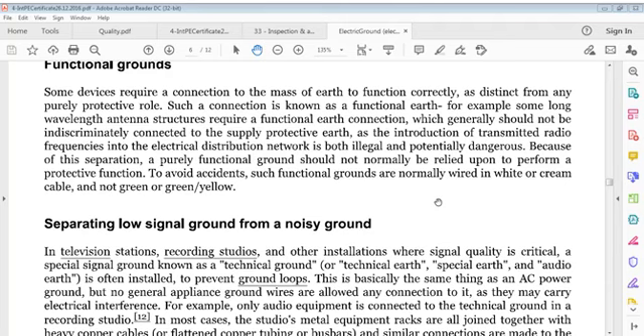What is the reason for that? Some long wavelength antenna structures require a functional earth connection, which generally should not be indiscriminately connected to supply protective earth, as introduction of transmitted radio frequencies into the electrical distribution network is both illegal and potentially dangerous. Because of this separation, a purely functional ground should not normally be relied upon to perform a protective function. To avoid accidents, such functional grounds are normally wired in white or cream cable and not green or green-yellow.